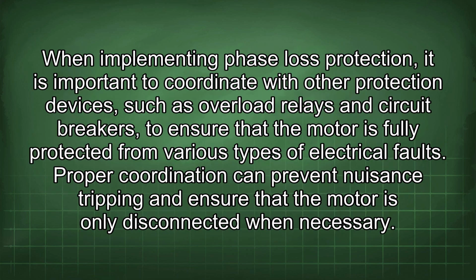When implementing phase loss protection, it is important to coordinate with other protection devices such as overload relays and circuit breakers to ensure that the motor is fully protected from various types of electrical faults. Proper coordination can prevent nuisance tripping and ensure that the motor is only disconnected when necessary.